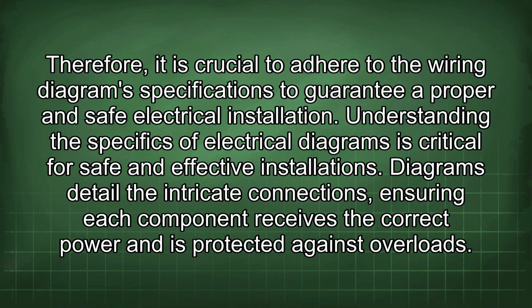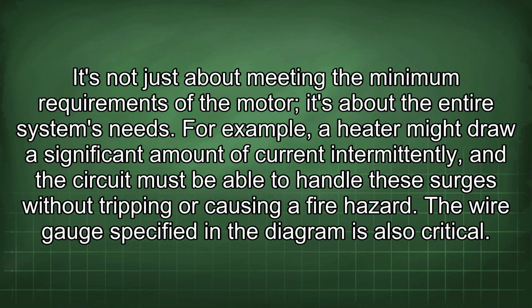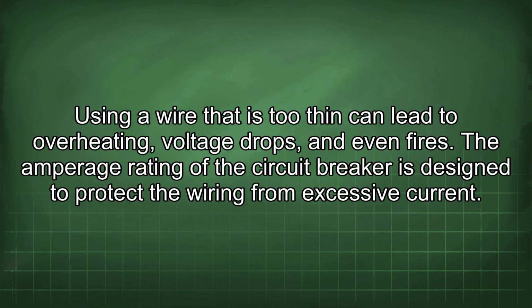Diagrams detail the intricate connections, ensuring each component receives the correct power and is protected against overloads. It's not just about meeting the minimum requirements of the motor, it's about the entire system's needs. For example, a heater might draw a significant amount of current intermittently, and the circuit must be able to handle these surges without tripping or causing a fire hazard. The wire gauge specified in the diagram is also critical. Using a wire that is too thin can lead to overheating, voltage drops, and even fires.